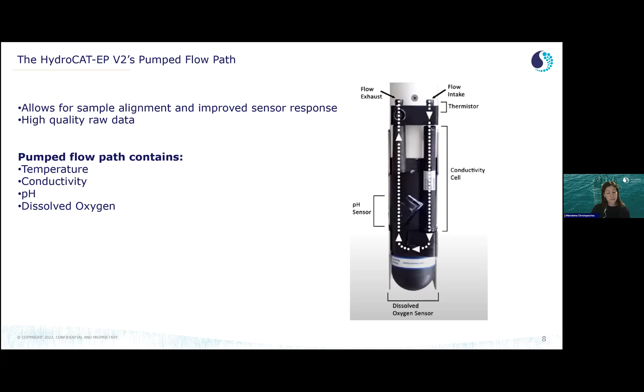As with most Seabird instruments, CTDs of course, the HydroCAT-EP V2 has the unique pump technology, the signature, I would like to say, of the Seabird CTDs. What this means is that water is pulled in the flow path, where a pump connects the temperature, conductivity, pH, and dissolved oxygen sensors. And every sampling interval, every few minutes, water is pulled in the flow path, so all these 4 parameters are measured in the same parcel of water. This controlled flow rate matches the time response of the different sensors and generates the most accurate raw data, something that is also very important for further calculation of parameters such as salinity.